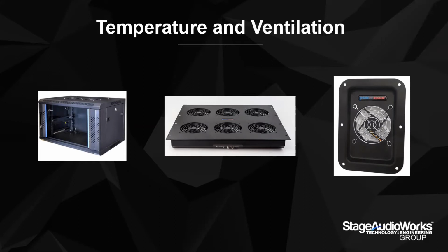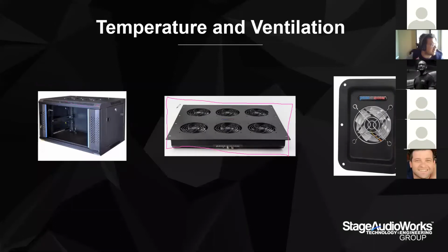Dust or bad ventilation could cause fans internally to ramp up to full speed continuously, which is not good all of the time. If the units are stored in racks and airflow is limited, then adding something helps. Just as an example, a basic little 19-inch rack normally doesn't ship with fans, but it does ship with extractor holes at the top of it. So you can order these racks with fans pre-installed, or you can add your own extractors depending on what equipment you're installing in the rack and what heat dissipation requirements you have. I know it means more cleaning from a fan perspective, but it will definitely help in the long term with the reliability of the gear. So these are just something you can build into 19-inch racks.